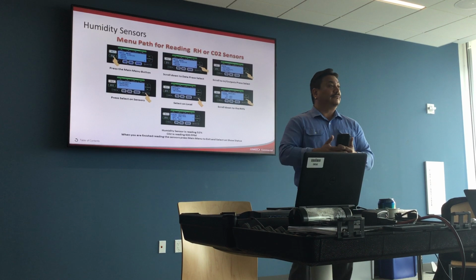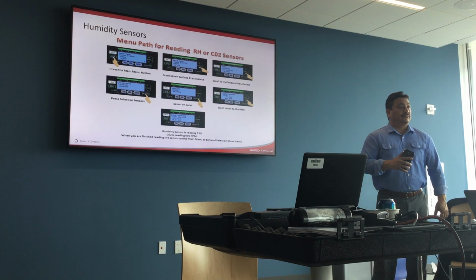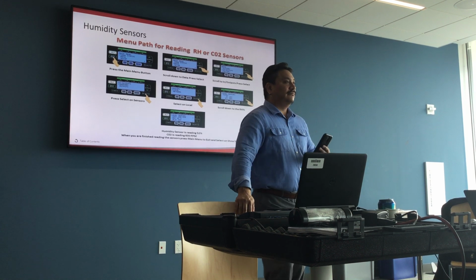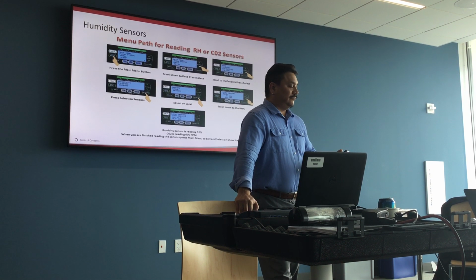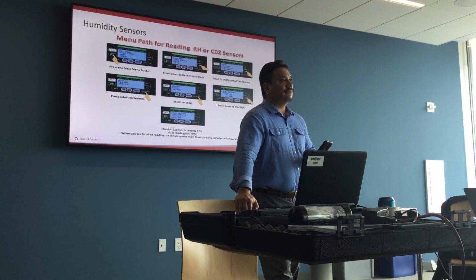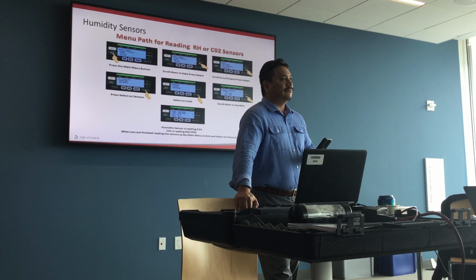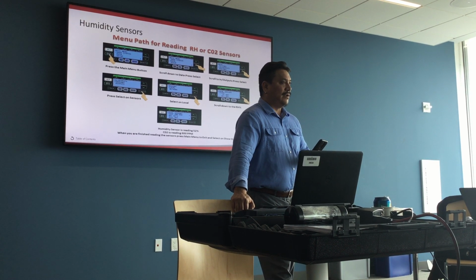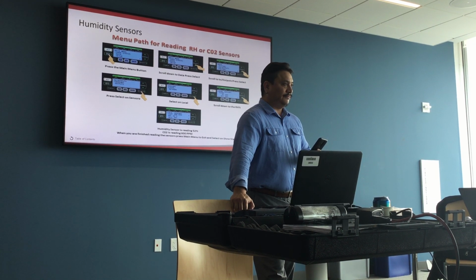Can I actually share something real fast? For example, in the Midwest and more east, obviously these units are more predominant, right? We get an alarm code, I'm making it up, you probably know the alarm code, 87 or whatever, it's Humiditrol, or there's like a damper close. So let's say you guys get a work order, now the auto assignments go to you first, you can get a ticket that says, hey, no airflow, get someone in here or something, right? It could potentially have that alarm, you guys could check that alarm and be like, oh, a fire smoke damper's closed. Okay, so when you go troubleshoot or decide to send a vendor or however you remedy, you guys are doing remote diagnostics and targeting specifically what needs to be fixed versus going there, putting on gauges, taking your temps, and kind of chasing a ghost.